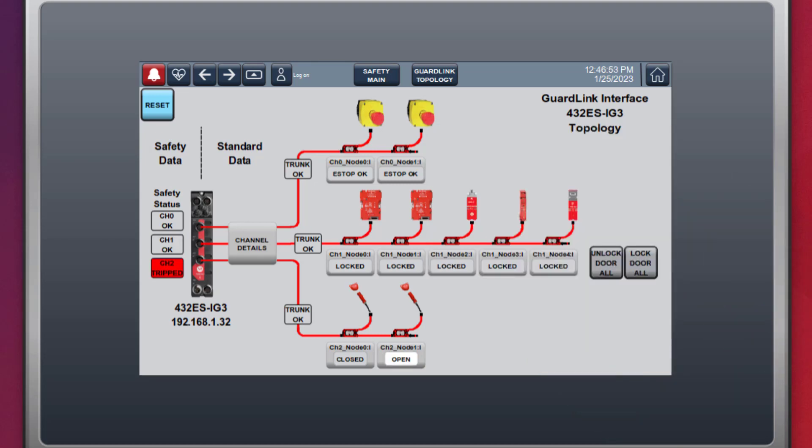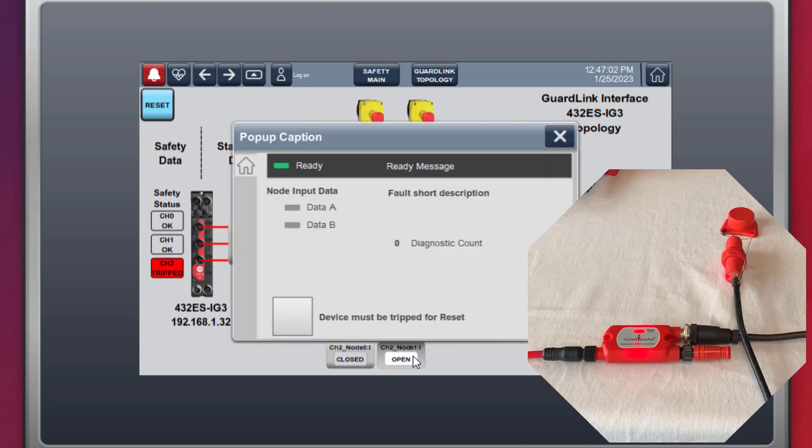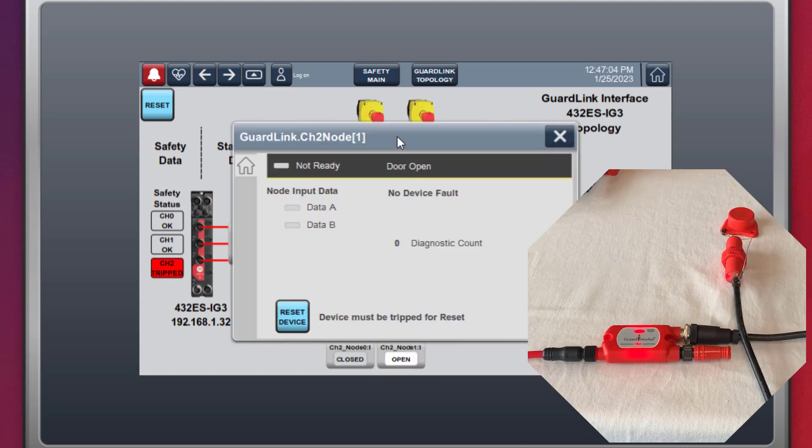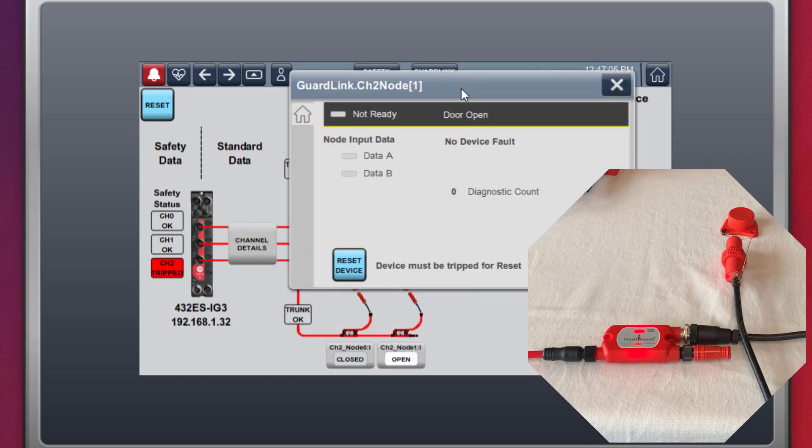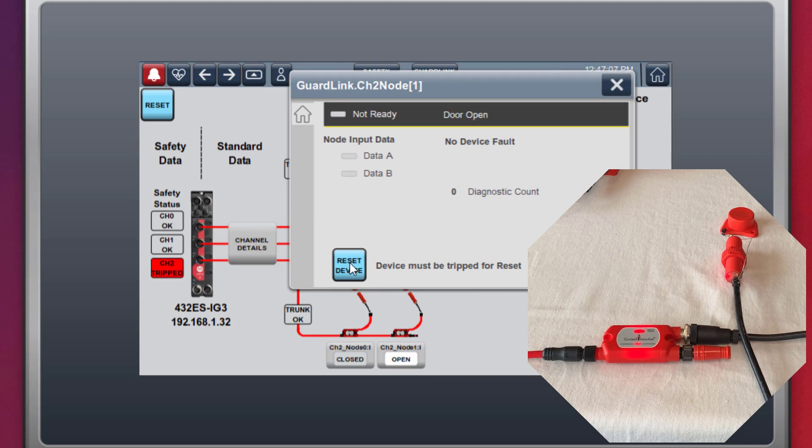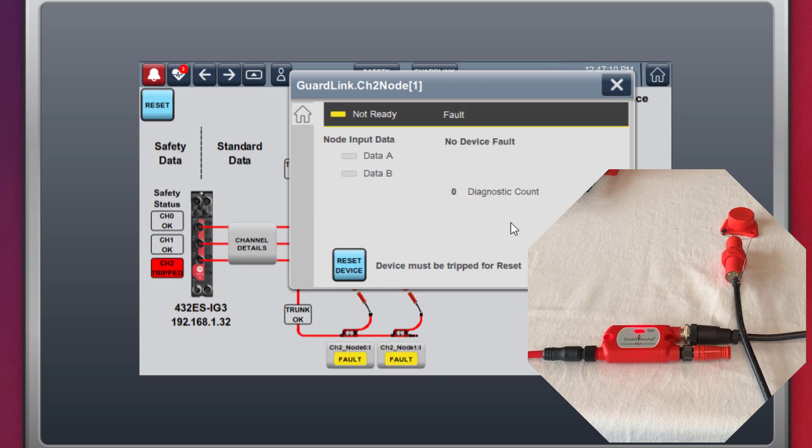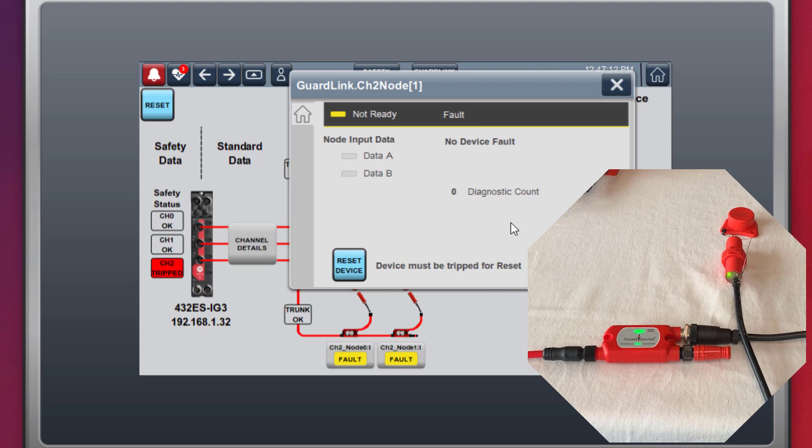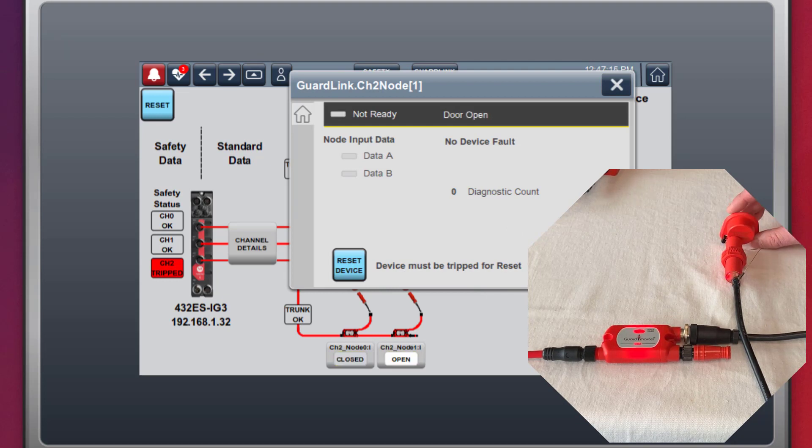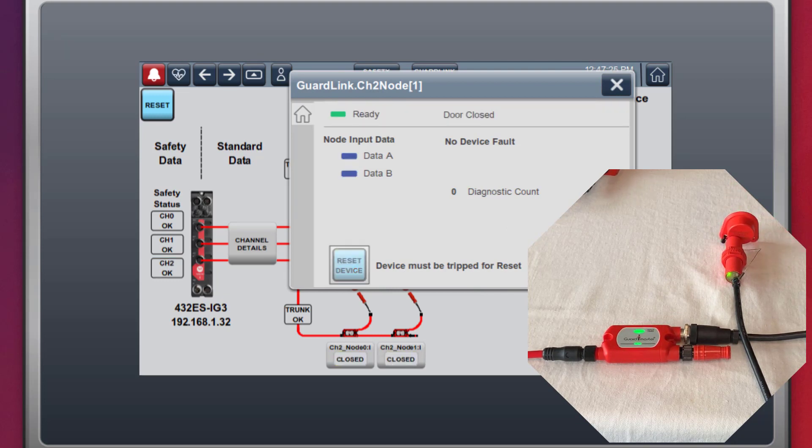Non-locking guard doors have similar capability as a locking guard door but without the lock and unlock feature. Here we will demonstrate the device reset function. The node device must be tripped for a reset. Pressing the reset push button power cycles the device. Notice that all devices on the GuardLink channel go to a faulted state during a power cycle.